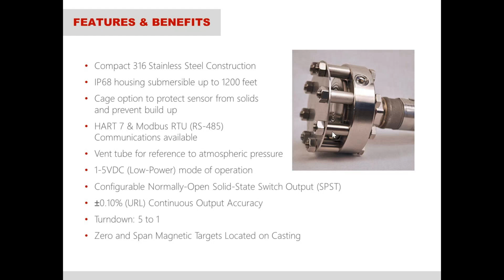This cover plate and this cage is just there to protect it from any type of floating debris, as well as when they're lowering the transmitter into the tank or vessel or whatever it is, so it doesn't damage it when it hits the bottom of the tank or the bottom of a well or whatever it is. Again, it has that vent tube for reference to atmospheric pressure and different options as well.